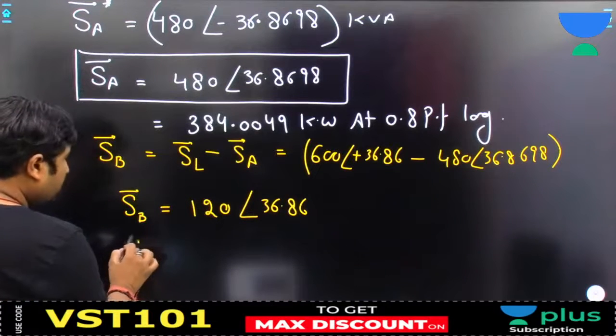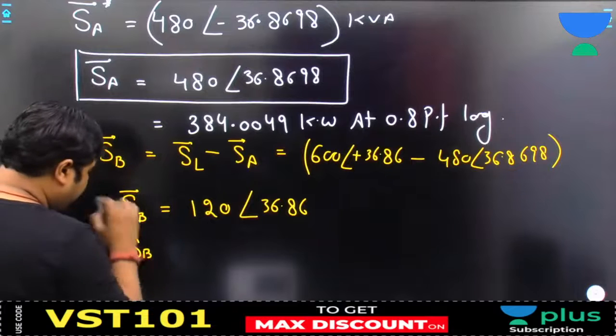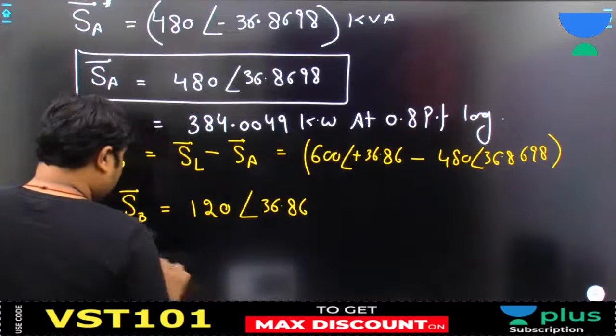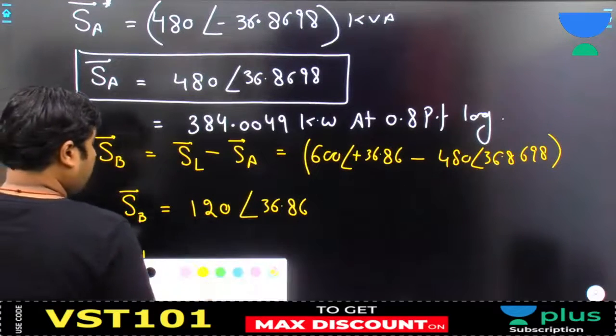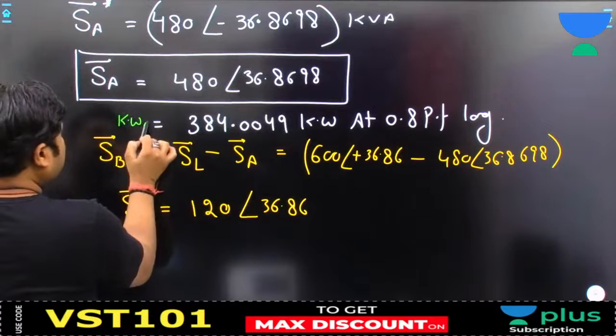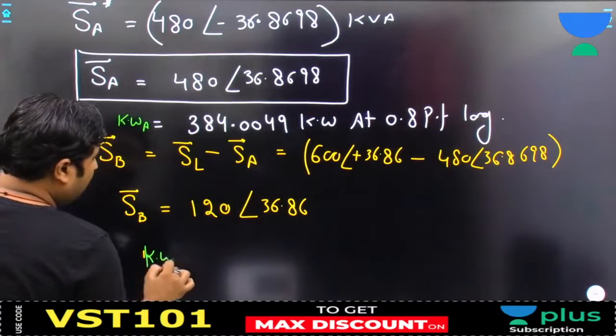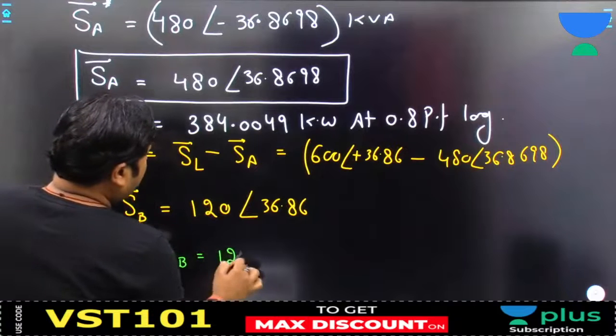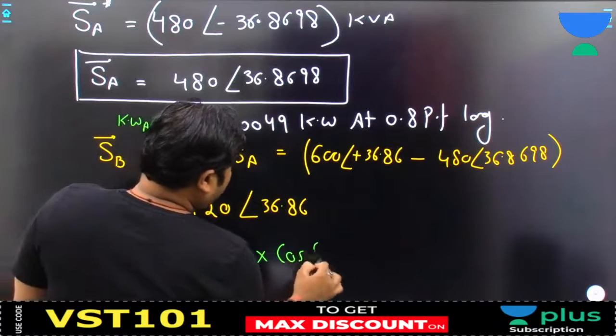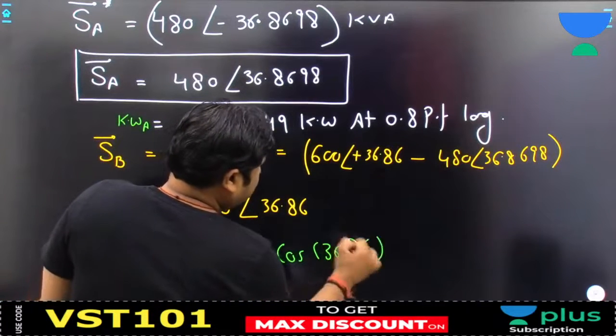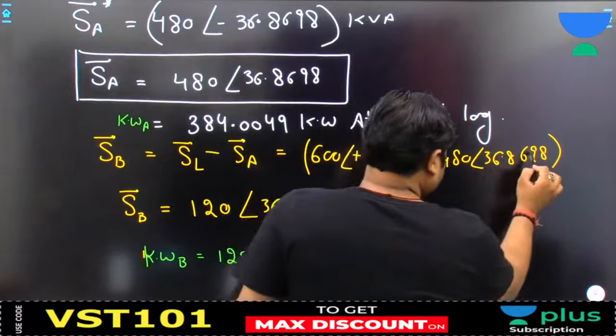So that gives 120 at an angle of 36.86 degrees. Is it okay? So we have kVA shared by transformer B, and kilowatt shared by transformer B. This is kilowatt shared by transformer A. You can calculate kilowatt shared by transformer B as 120 into cos of 36.86.